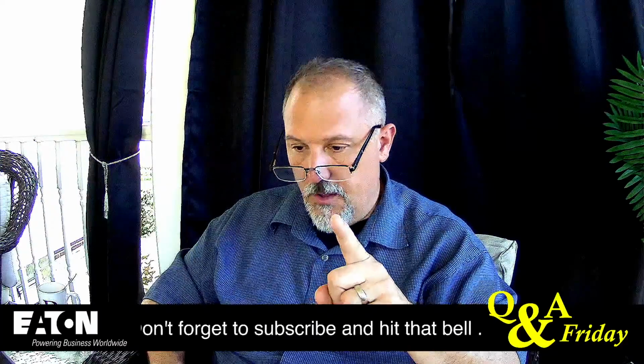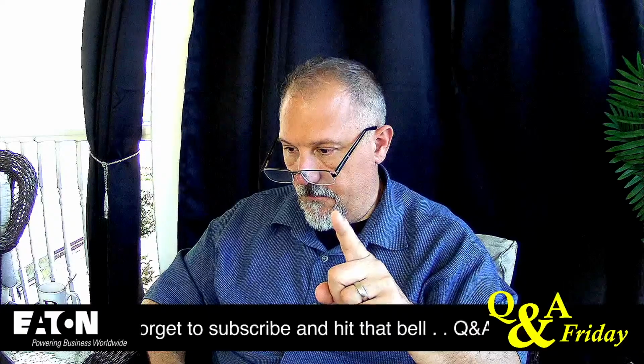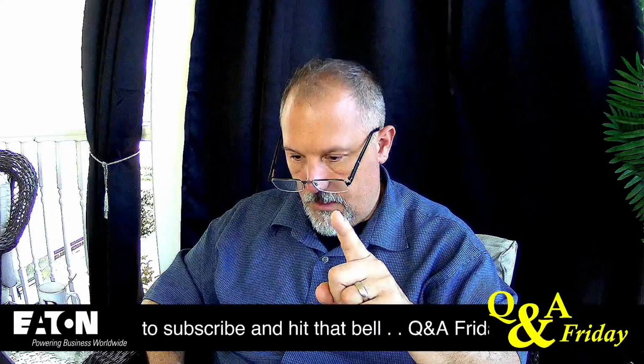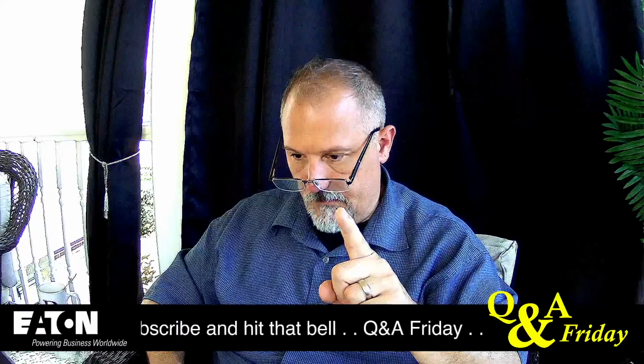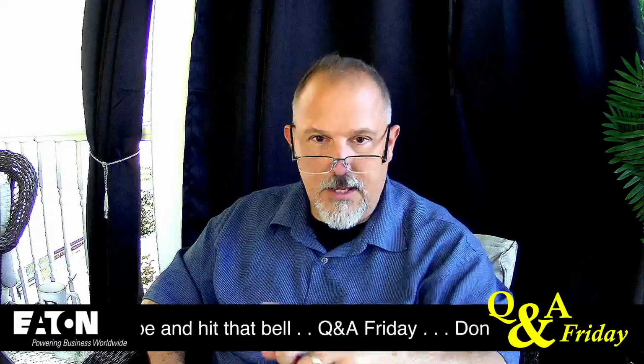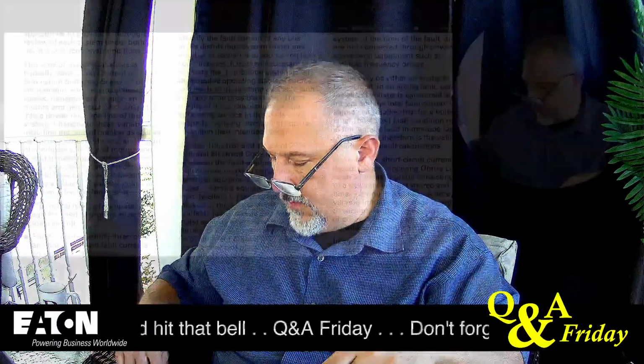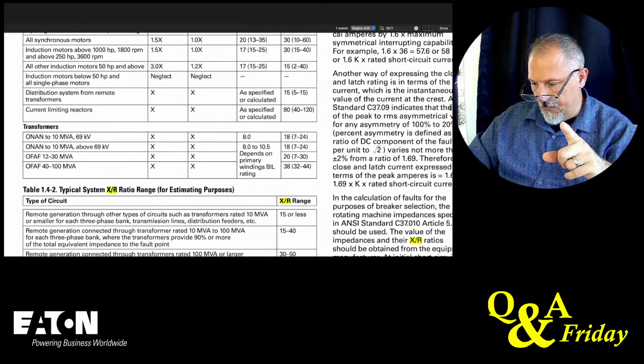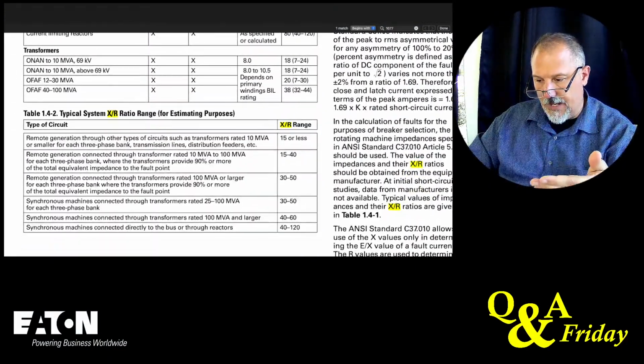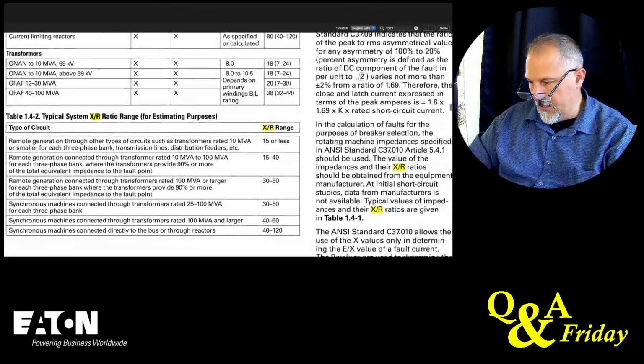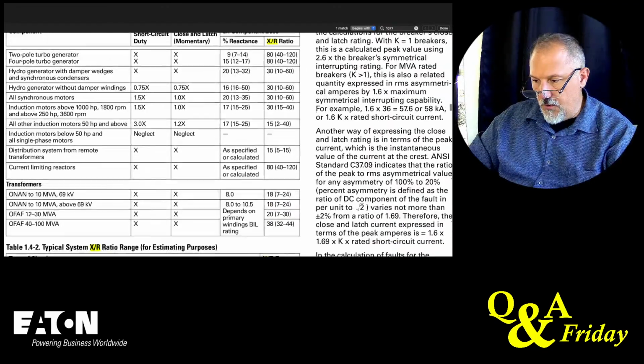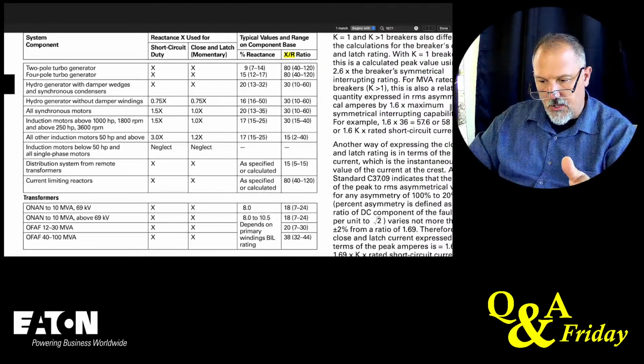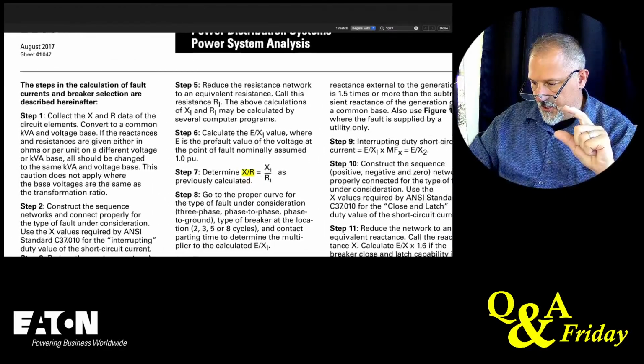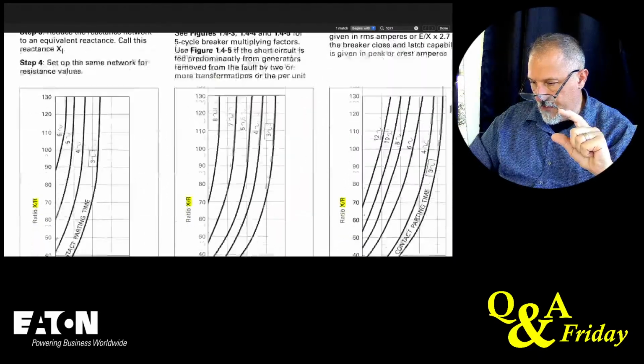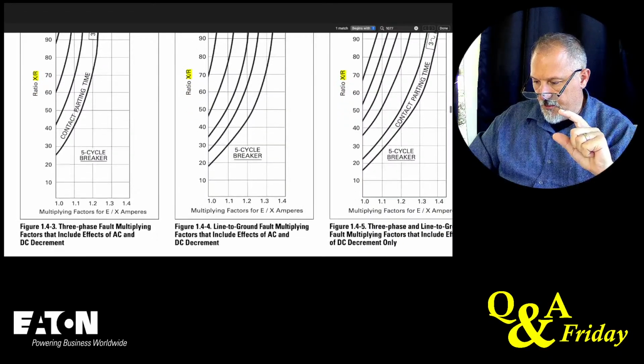Now, it's very rare that you will... Here we go. I think this is it. Hold on. Yeah, see, look, in that reference that I just gave you, there's even more good information in there. Look at this. They'll tell you the typical system X to R ratios for estimating purposes, right? They'll give you two-pole turbo generators, what the X to R ratio is. You can a lot of times get this from the manufacturers. There's your steps, there's your determining your X to R ratio, and these are your multiplying factors.